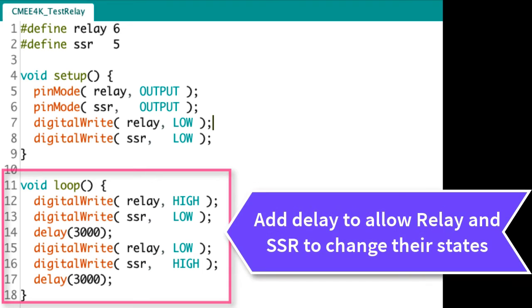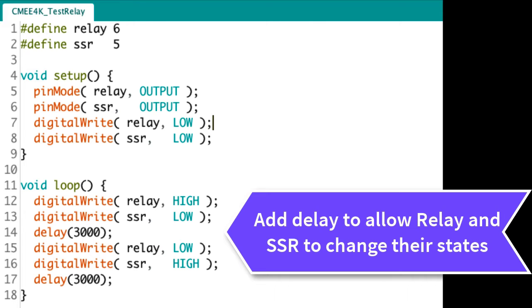In general, we need to add a delay function for these devices to react. From my experience, at least 250 milliseconds delay is needed for the devices. In this example, we added a 3000 millisecond delay, which is 3 seconds.